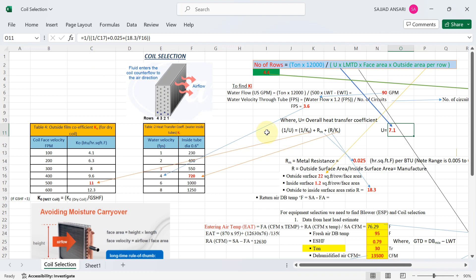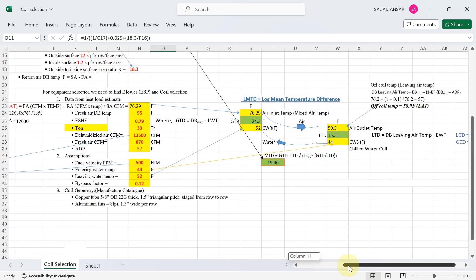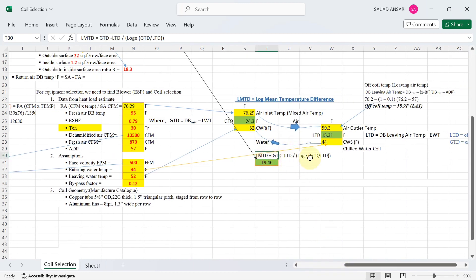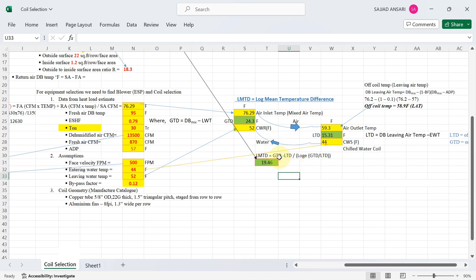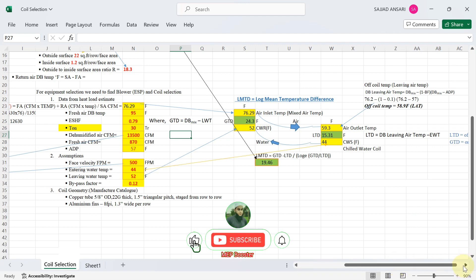Now we need to calculate the log mean temperature difference (LMTD). The formula is: LMTD = (GTD − LTD) / ln(GTD/LTD), where GTD is the greatest temperature difference and LTD is the least temperature difference. To find GTD, the formula is: GTD = DB mix (on-coil temperature) − leaving water temperature.